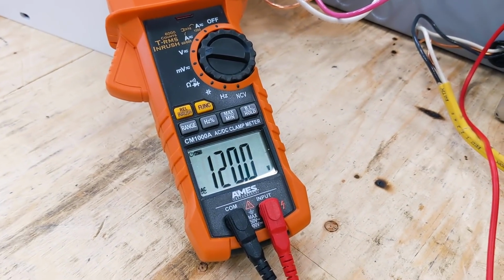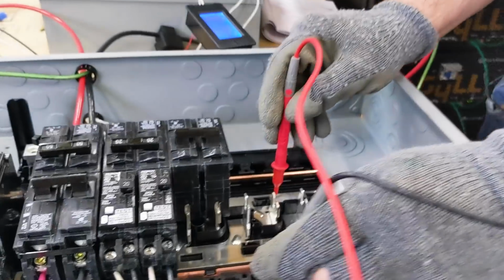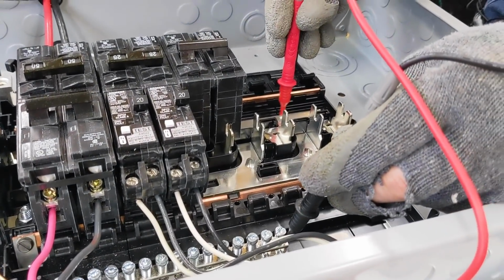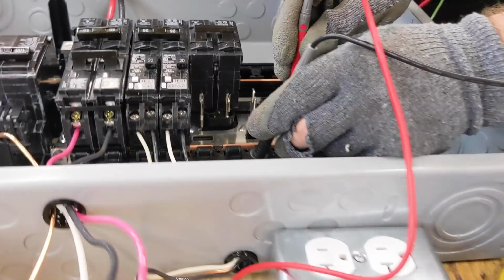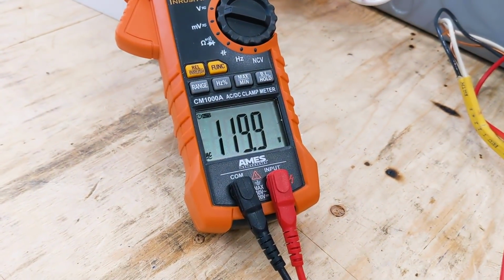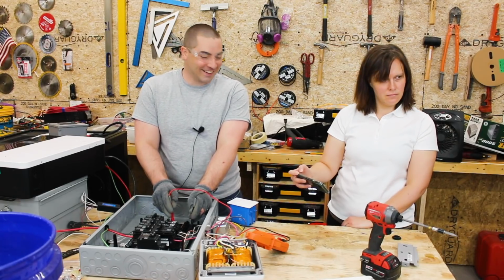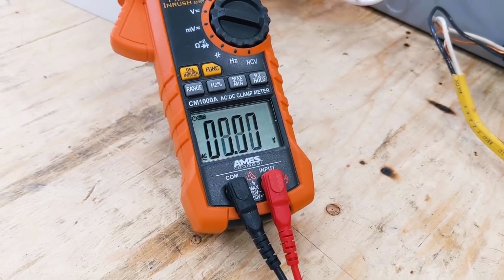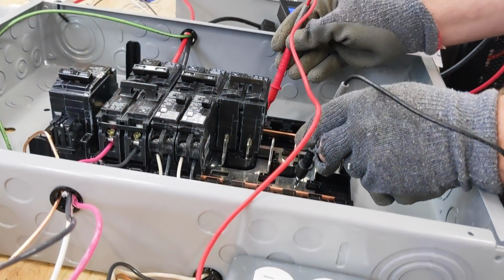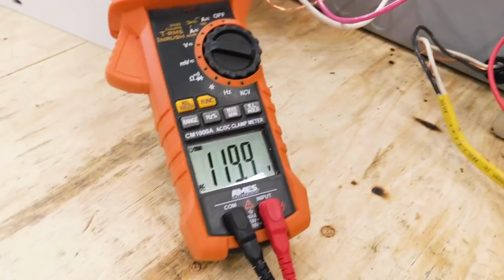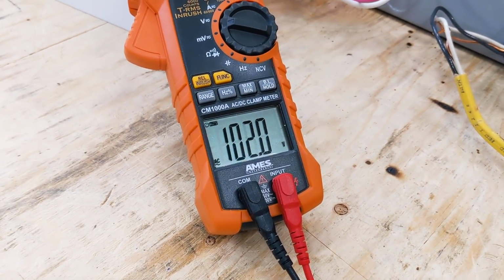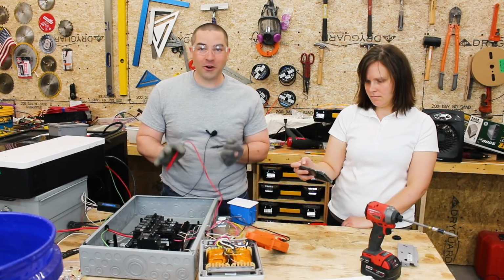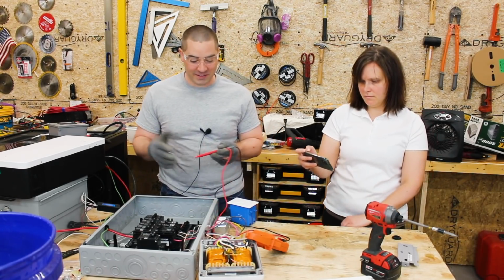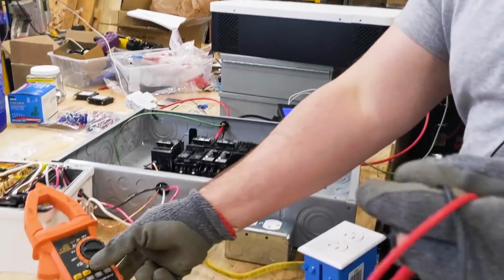All right, let's check the other bus bars. I'm keeping one probe on the neutral bar, and I'm jumping to the other hot leg. It's also 120. We did it! All right, now let me check to the other neutral bar, because there's two neutral bars in this, and they should be connected. Yes, they are. Jumping over, 120. So we totally did it. We have 120 volts. Oh man, that's awesome.